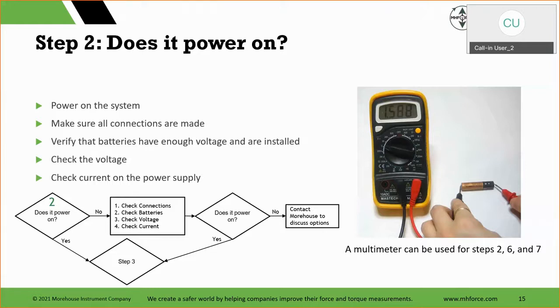Some meters compensate, some do not. There's a whole list. We don't know them all. So instead of doing studies and everything else that would take years, we just replace the batteries, so we're sure. And we still do the occasional check: hey, I wonder what happens if we use the old versus new batteries. In one case, pretty recent, we found that the instrument needed adjusted with the old batteries. We put the new batteries in, and it was spot on where it needed to be, or close to it. So that's a lesson. But yes, verify that the batteries have enough voltage.